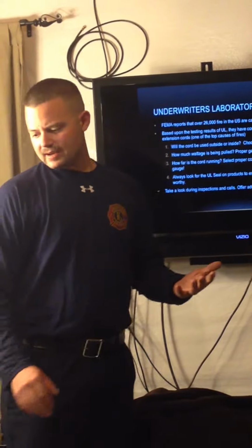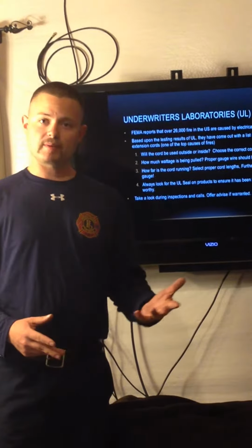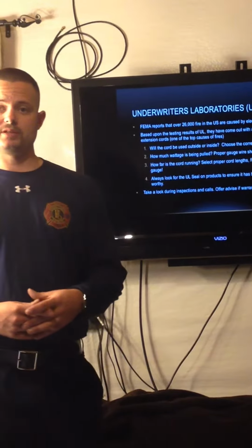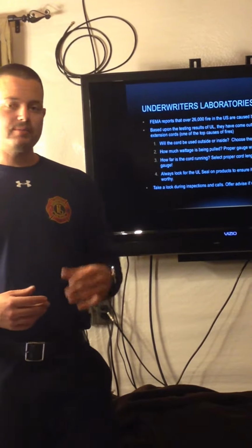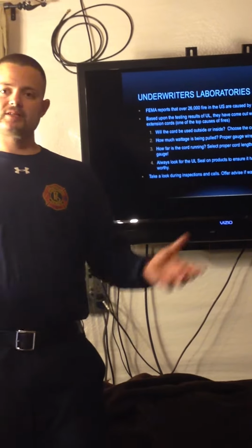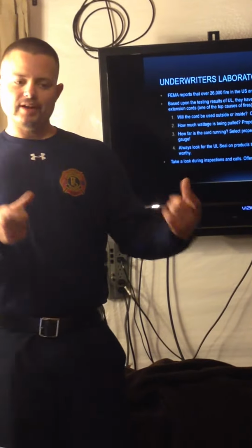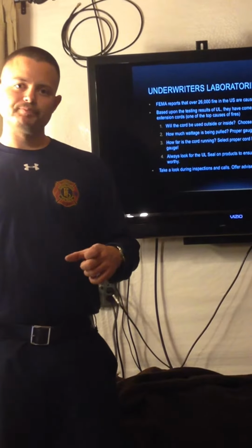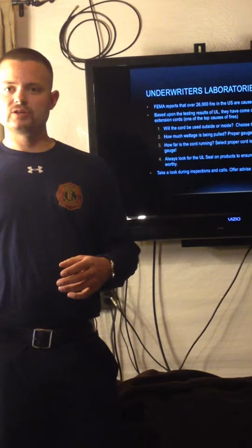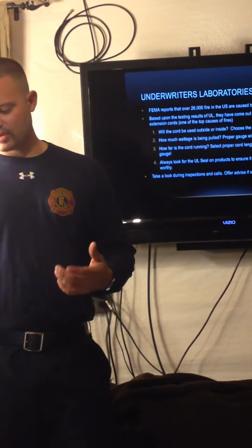On the fire side, we want to take a good look while we're doing our business inspections through the year. I know with the department I'm with, we perform over 250 business inspections a year. We do take this time to make sure we look in depth at all electrical appliances going through. We're not necessarily going to ding you if they're UL or not, but we want to look for extension cords. If we have our power outlet strips with another power outlet strip plugged into it, we don't want to do that. Having proper gauge, if it's a refrigerator, we have a good cord. Those are the kind of things we want to keep our heads up for.